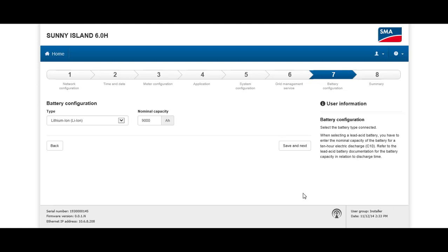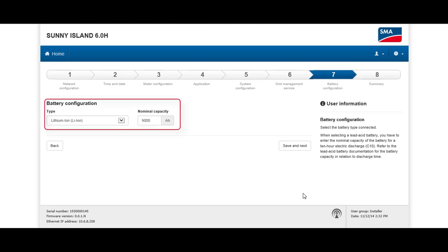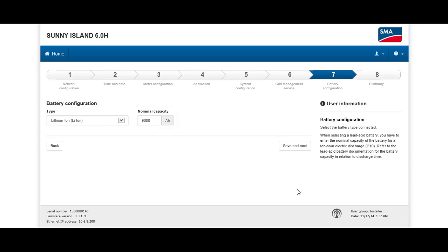This is the final step of the whole setup: battery configuration. The Sunny Island product family includes integrated battery management for lead-acid batteries of type FLA (flooded lead acid) and VRLA (valve regulated lead acid). It is also possible to connect an external battery system, typically used with other battery technologies like lithium-ion. You can find a list of currently approved battery manufacturers and types in the download section of the homepage. Here we choose battery type lithium-ion and enter its rated capacity so the Sunny Island knows what it's working with.